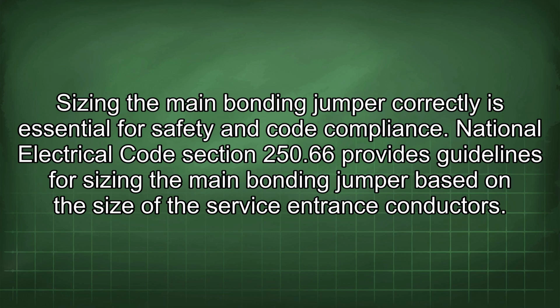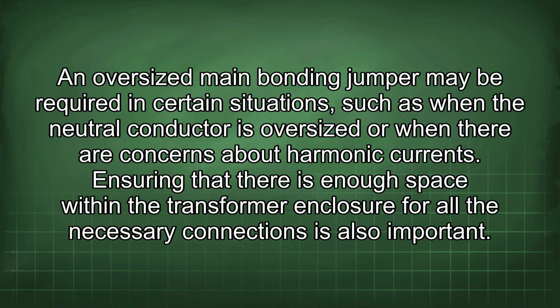National Electrical Code Section 250.66 provides guidelines for sizing the main bonding jumper based on the size of the service entrance conductors. An oversized main bonding jumper may be required in certain situations, such as when the neutral conductor is oversized or when there are concerns about harmonic currents. Ensuring that there is enough space within the transformer enclosure for all the necessary connections is also important.